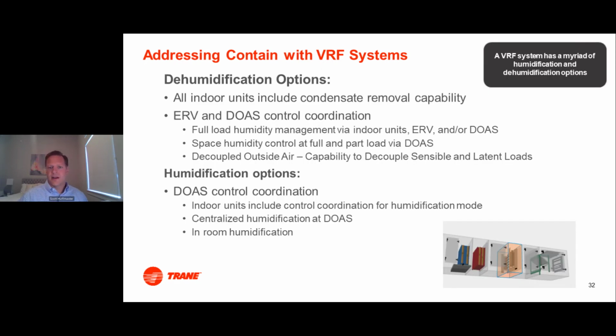So one of the reasons I really like a VRF system for this is not only can we do a really good job of dehumidifying, do that centrally at your DOAS unit, potentially look at handling not just all your outside air, but maybe decouple your entire outside air and your sensible and latent all in that DOAS unit. Remove the latent from your outside air, but also remove that latent heat or that latent load from the space with that DOAS unit. You can do that centrally, and you can really optimize that with the VRF system.